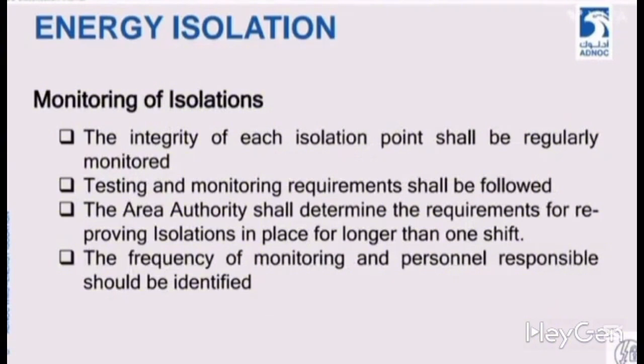How and why should we monitor the isolation? The integrity of each isolation point shall be regularly monitored. If our activity is running for more than one shift, we need to validate our permit in every shift by getting the isolation certificate validated before revalidation or making it live. For the isolation certificate to be valid, zero energy must be demonstrated by the ISO to the JP. Only then will he sign the permit. Once your certificate is endorsed and validated, your permit can go live.